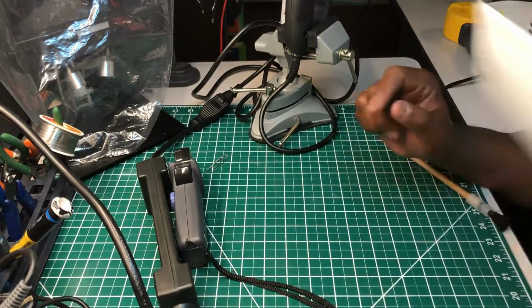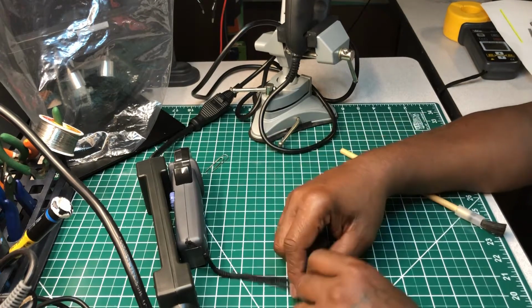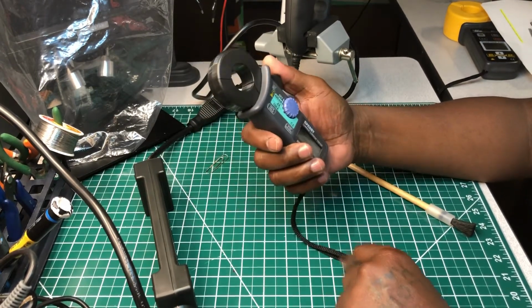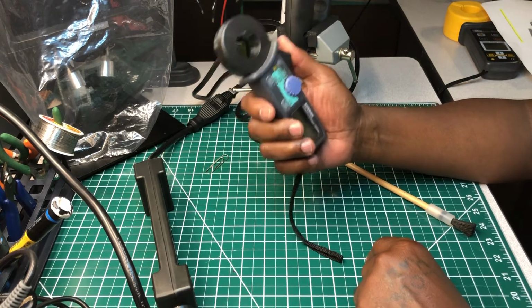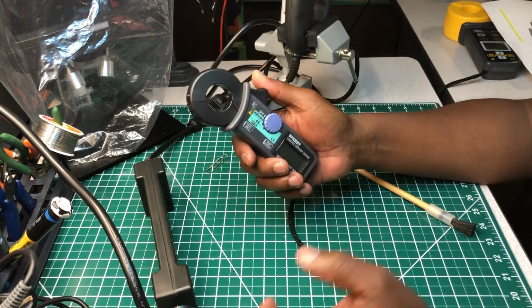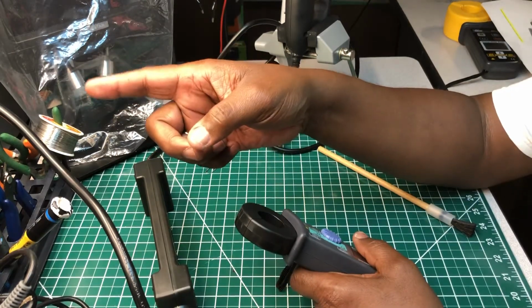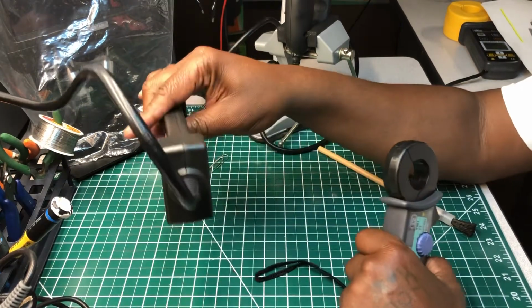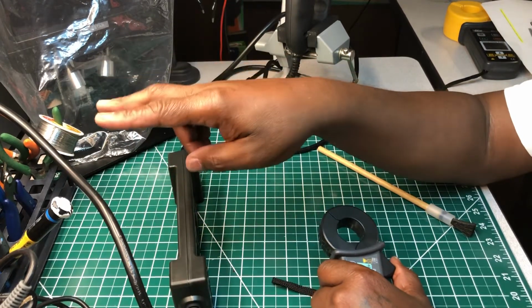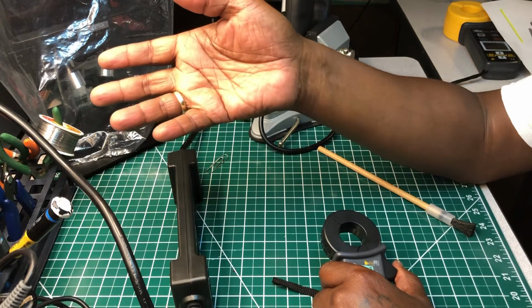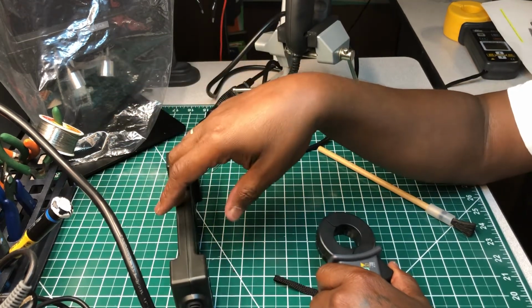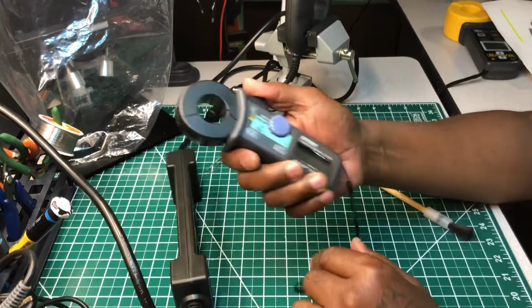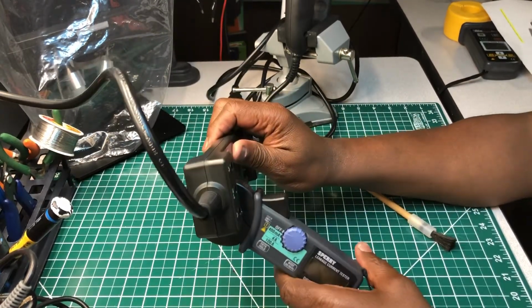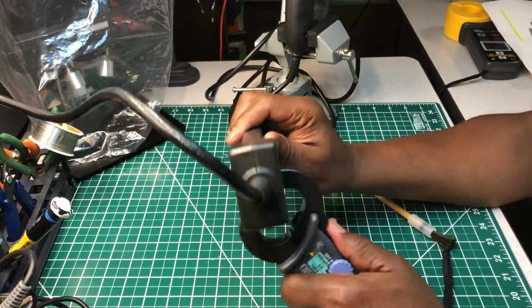Get it. So guys, not to hold you up any longer, I just wanted to show you how to use it. To use this, again, I repeat, you wrap these around the line and the neutral, either inside the panel, or you can unscrew the receptacle apart and put this around the two wires in the back, or you could buy yourself one of these, which I recommend. That way you don't have to pull another receptacle out, since the wires may not be as long as they're supposed to be, which is supposed to be 6 inches. Not as long as it's supposed to be, so now you've got to try to stick the head of this thing all inside the box. No, the best way is to get yourself one of these, and that would help you out, or go to the panel.